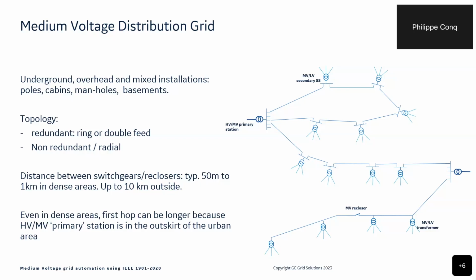In terms of topology, you have either redundant topologies - you can have rings, so an MV cable that comes from one primary station, goes around and comes back to the same one, or you can have some sort of backfeed between 2 primary stations. So wherever you're connected to the grid, you always have a backup cable, so you can be powered at any time. If there's something wrong on one cable, the power can come back from the other side.